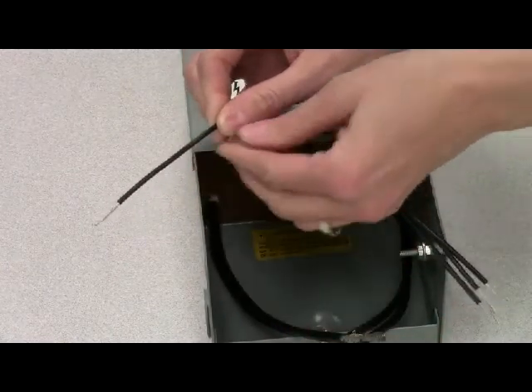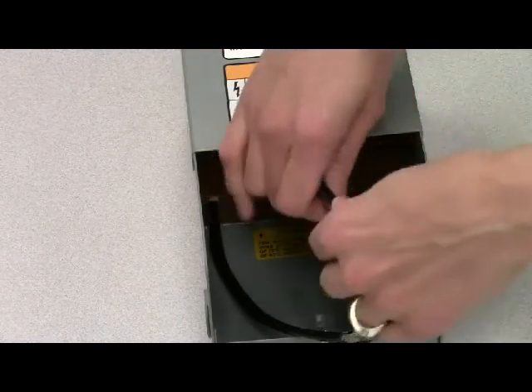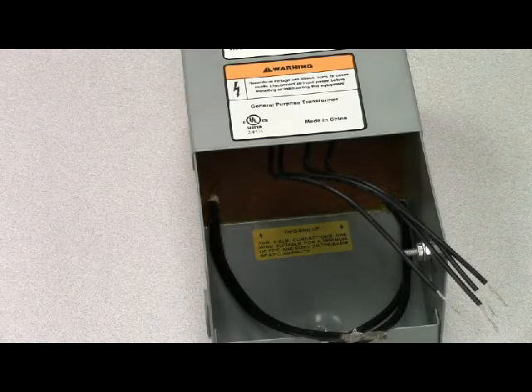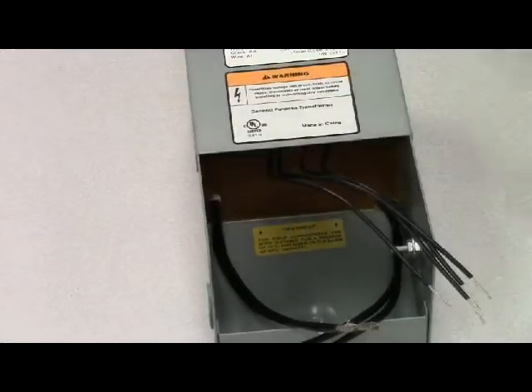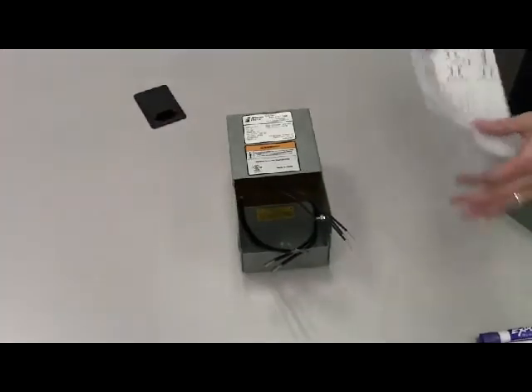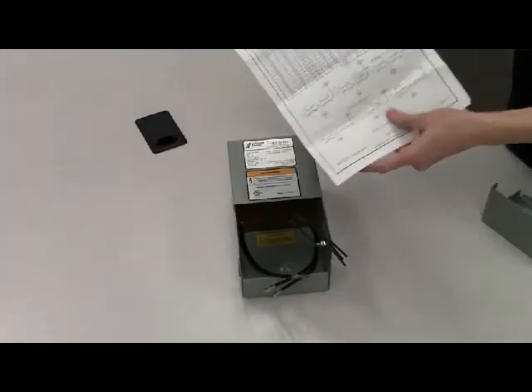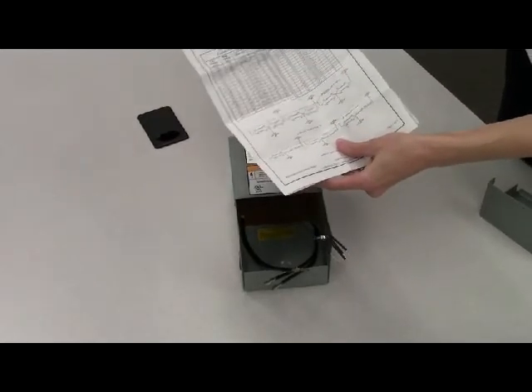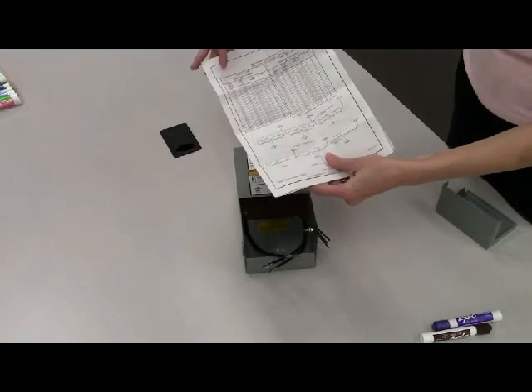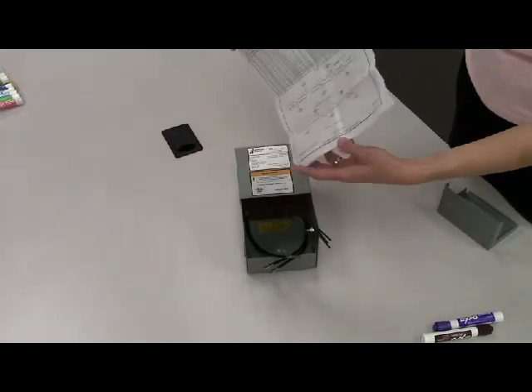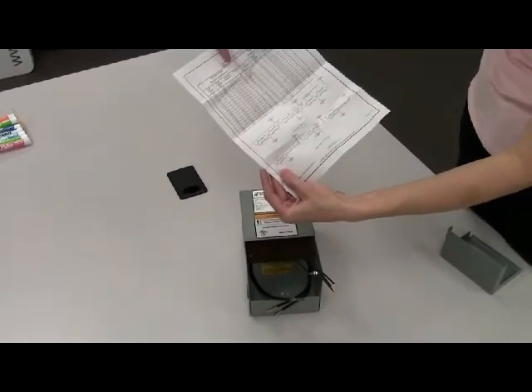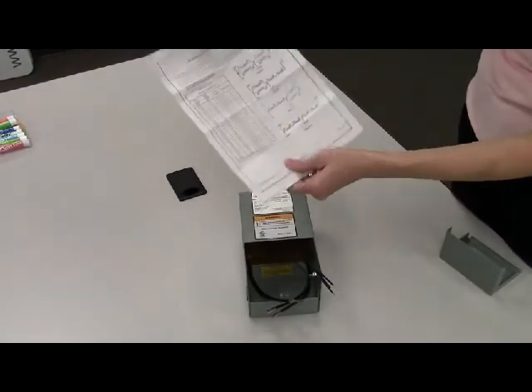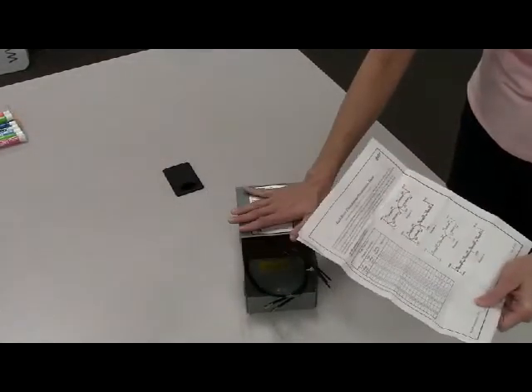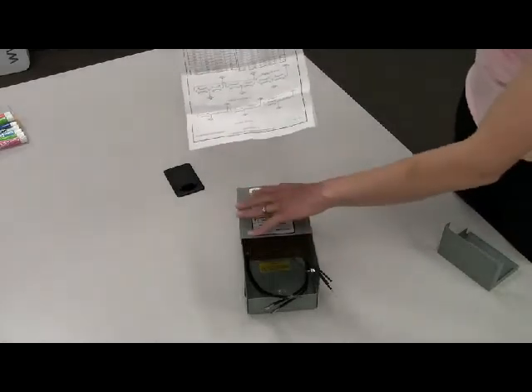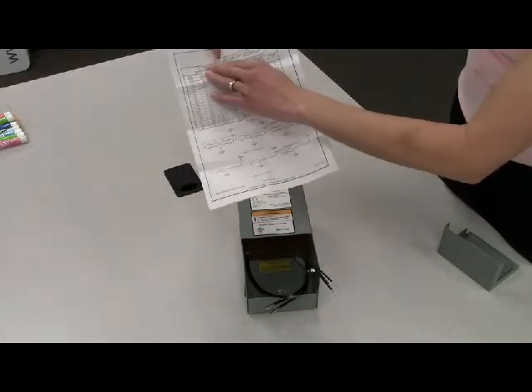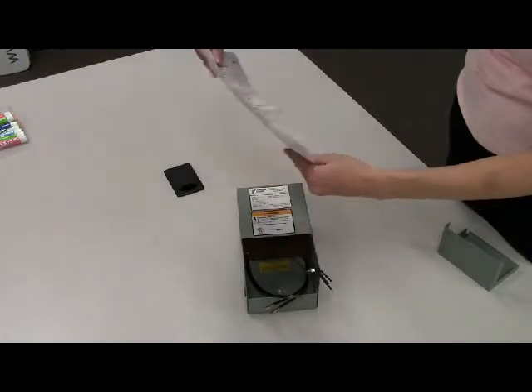But also, each of the wires is labeled on it, H1, H2, and so forth. So you can connect it using this diagram if you need. However, if you need to use it as a buck-boost transformer, it comes with wiring diagrams for all kinds of bucking and boosting applications, even in open delta or just a regular three-phase, and even a single-phase chart. Now this is a single-phase transformer. If you wanted to do one of these, you would need more than one transformer to hook it up in an open delta or a three-phase configuration.